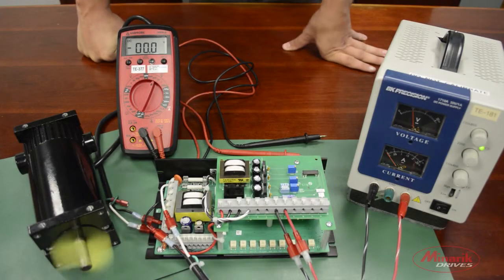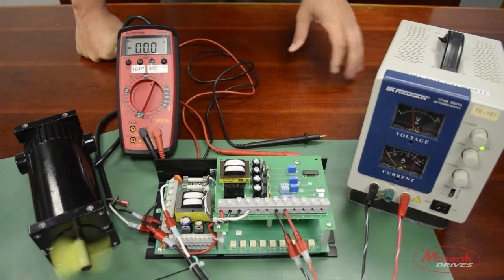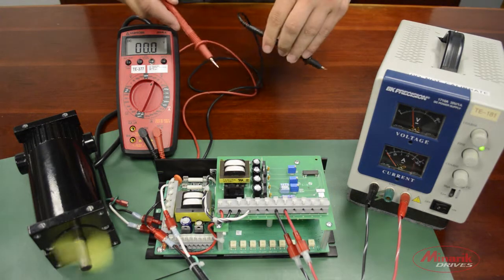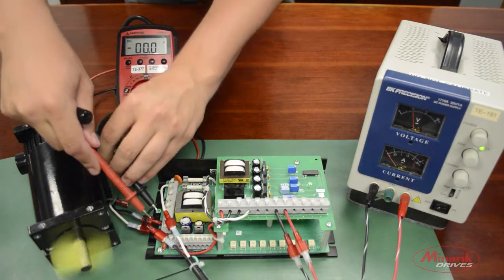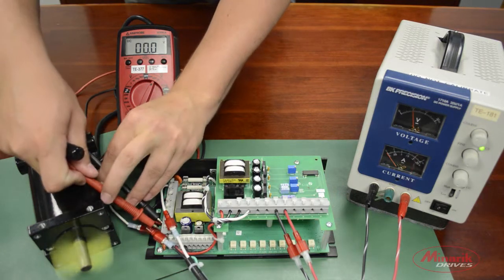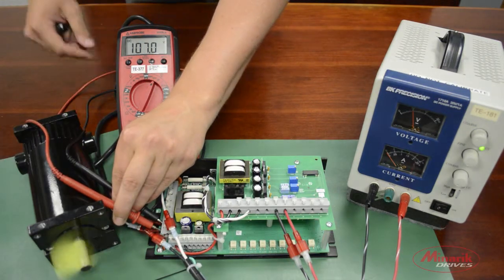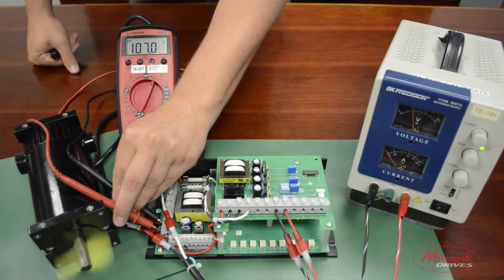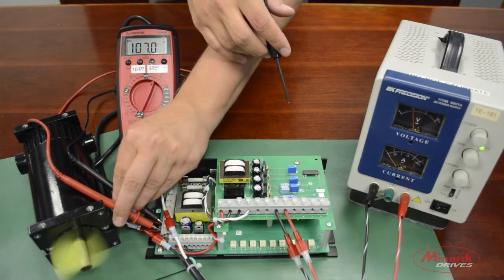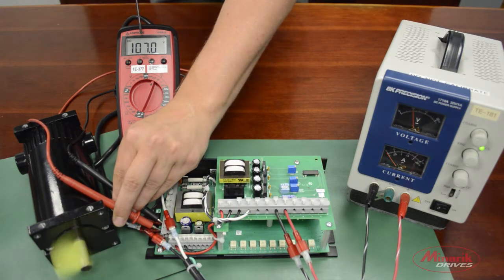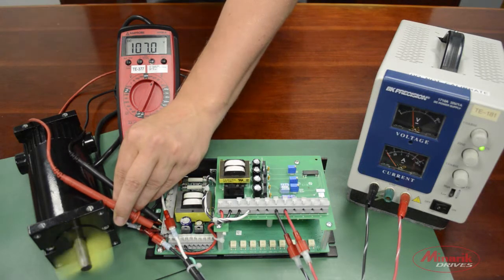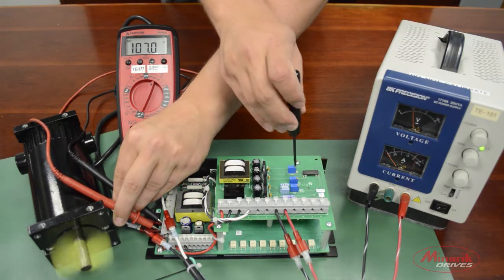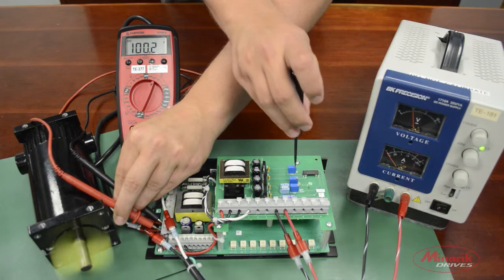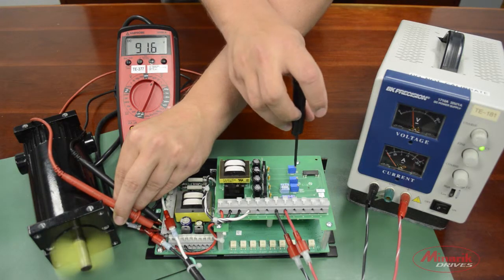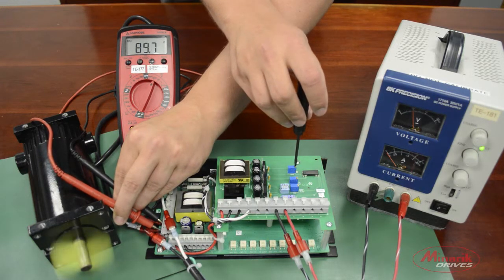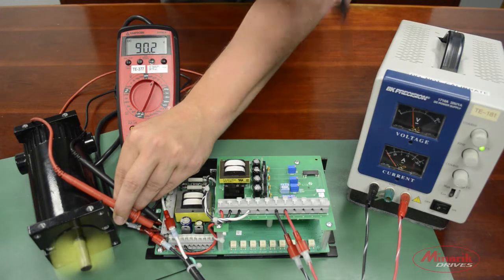The last step to calibrating the isolation card is to read across A1 and A2 while applying the max input signal. We'll now adjust the max out trim pot until we reach 90 volts on the multimeter, which is what this motor is rated for. We'll turn the trim pot counterclockwise until we reach 90 volts.